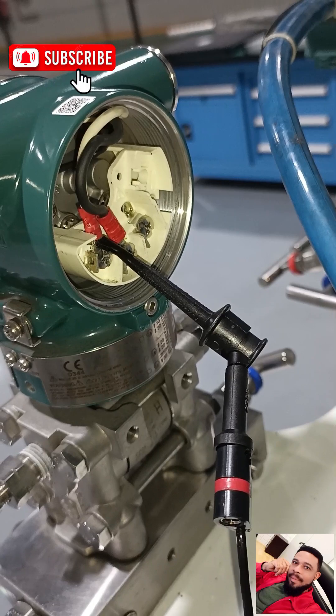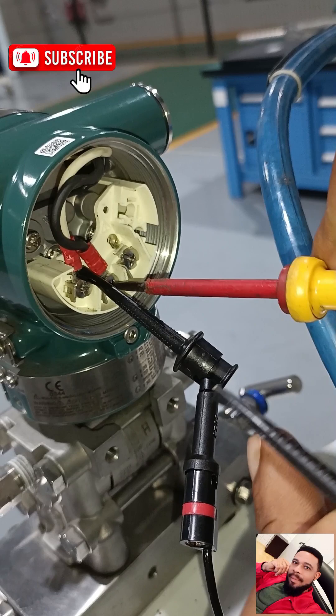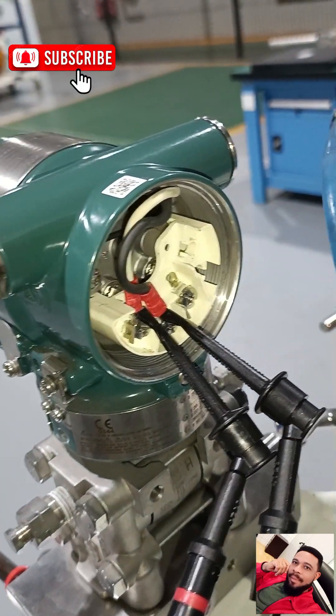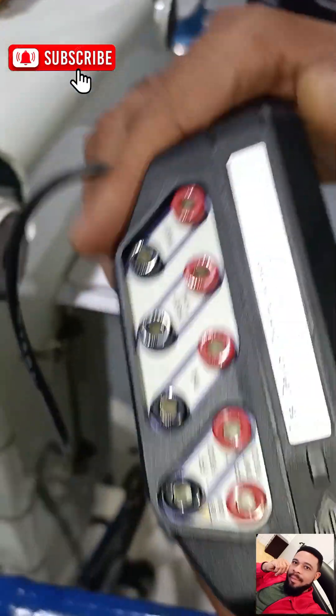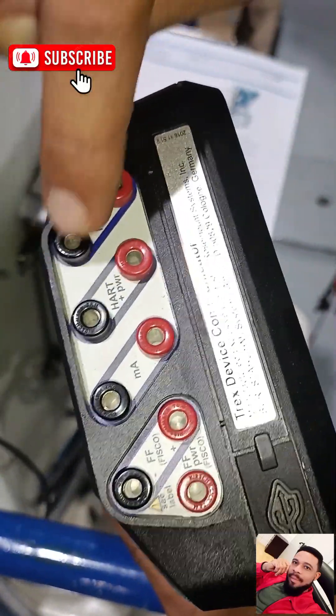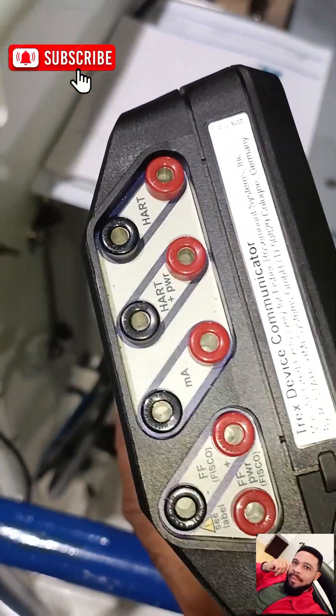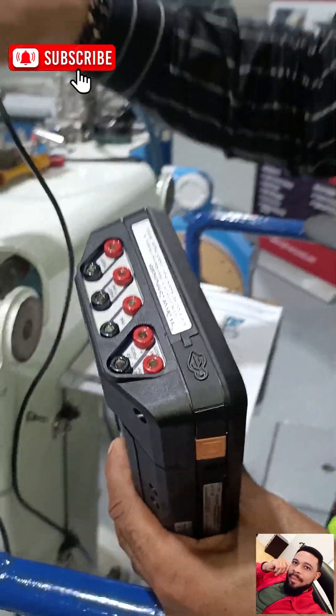Next, I open the negative terminal a little to create space and hook up my negative to that. We are done connecting to the transmitter. Now, looking at your AMS Trex, it has different ports. There's a HART port — you use this when you have an external power supply coming into your transmitter and you don't need to power it up; you just need to run your checks.